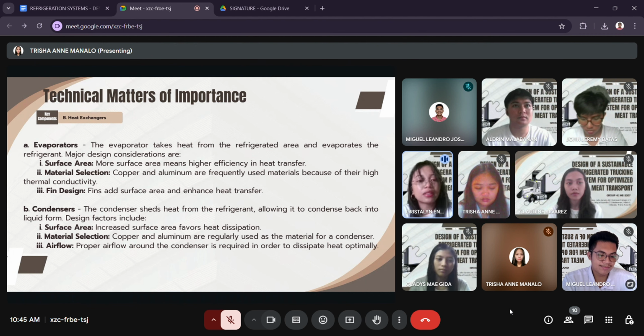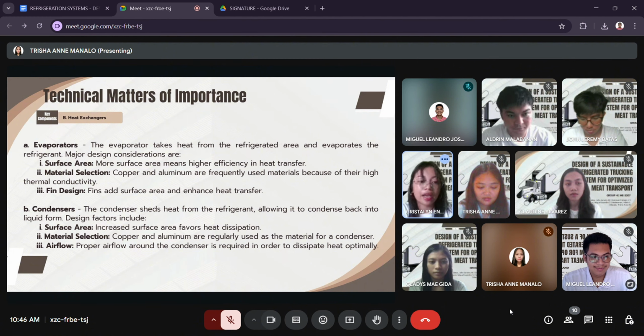Condenser. The condenser sheds heat from the refrigerant, allowing it to condense back into liquid form. The design factors include surface area, material selection, and airflow. In surface area, increased surface area favors heat dissipation. Copper and aluminum are regularly used as the materials for a condenser. Airflow. Proper airflow around the condenser is required in order to dissipate heat optimally.